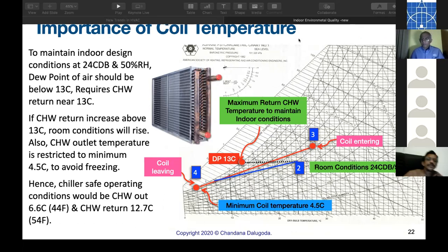What do they do? They raise the temperature. In a chiller, they raise the chill water temperature because they immediately get a saving. The power consumption will reduce dramatically. Of course, we know, because that is another proper energy saving method called chill water reset. But that is applied during part load conditions only. If an air conditioner is operating for 24 hours, yes, during night we would be able to do that. But unfortunately, during a hot sunny day, people operate the chillers at a higher temperature. We'll discuss further.